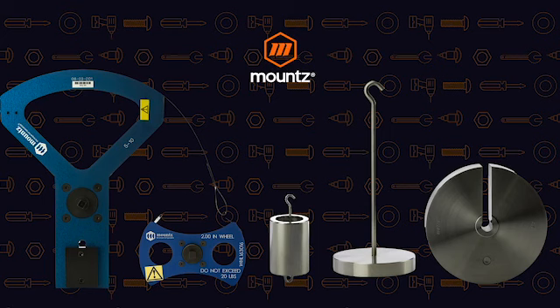And so in our typical torque formula, we have distance times force is going to equal what our torque value is. Now, there's a couple other calculations that go into it, like a specific gravity of where you're at, and that can change depending on your location, and that is a variable that is included within the actual process of doing the measurement for the different values that are being taken. But a typical 3-point calibration is going to test or apply load to the sensor at 10%, 50%, and 100%. And so by using the wheels and the weights, or the segment arms and the weights, we develop a value for that.